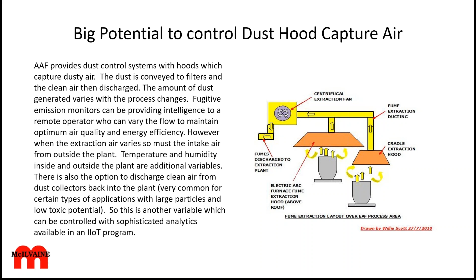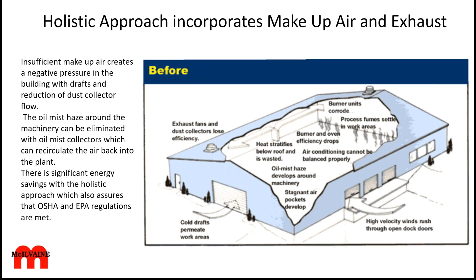So the way to look at all this, I think, is that with a holistic approach, you vary the amount of exhaust air that goes out through your dust collector systems based on cleanliness and other factors. You eliminate drafts and other issues by maintaining a pressure within the plant that's as close to zero as possible, or slightly positive. For things like oil mist, you have local dust collectors which collect those. In some cases all the exhaust goes outside; in others it's all recirculated, depending on the type of dust and conditions. Then you look at everything else within the plant too, and all of this can be remotely monitored and controlled.